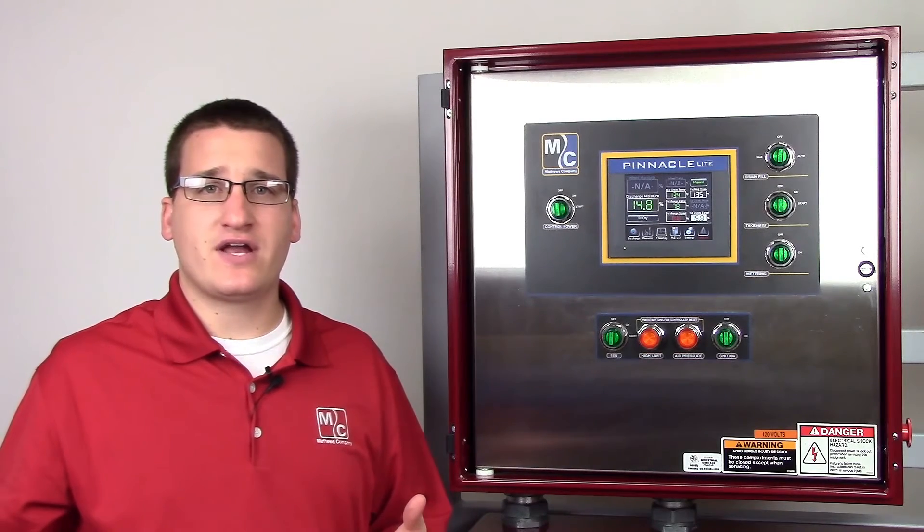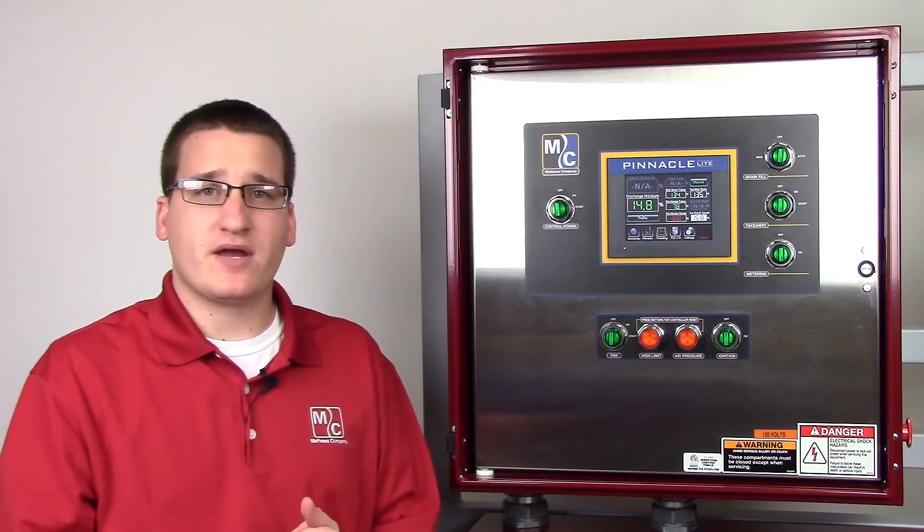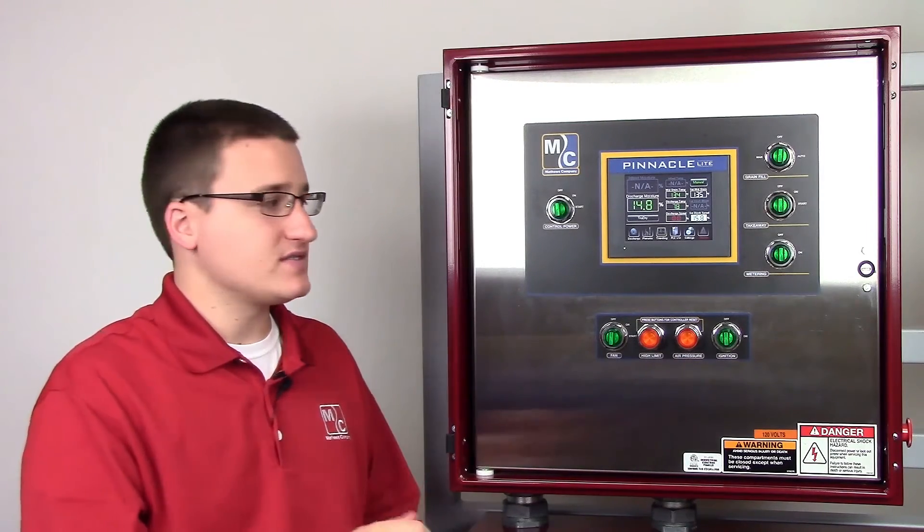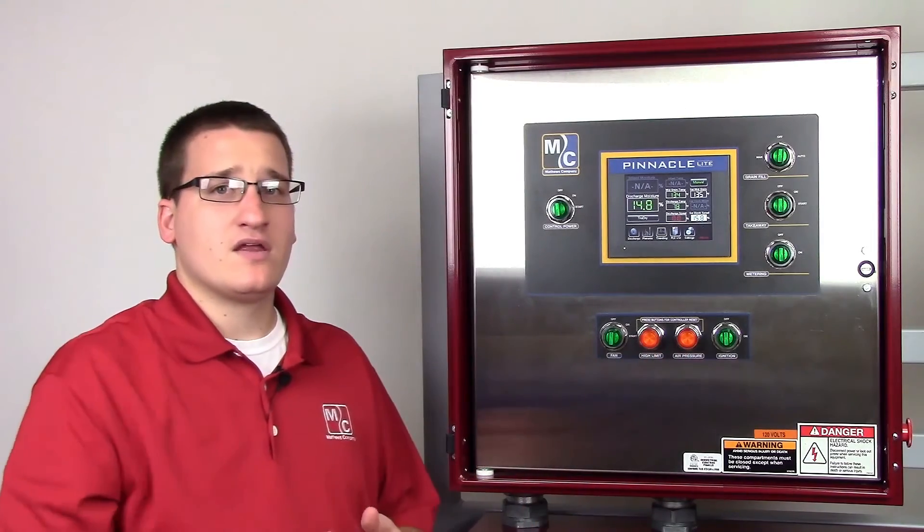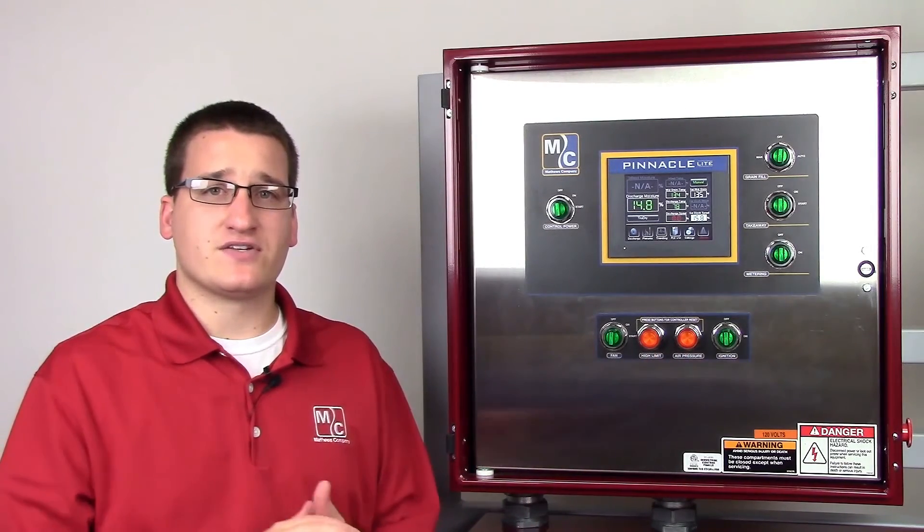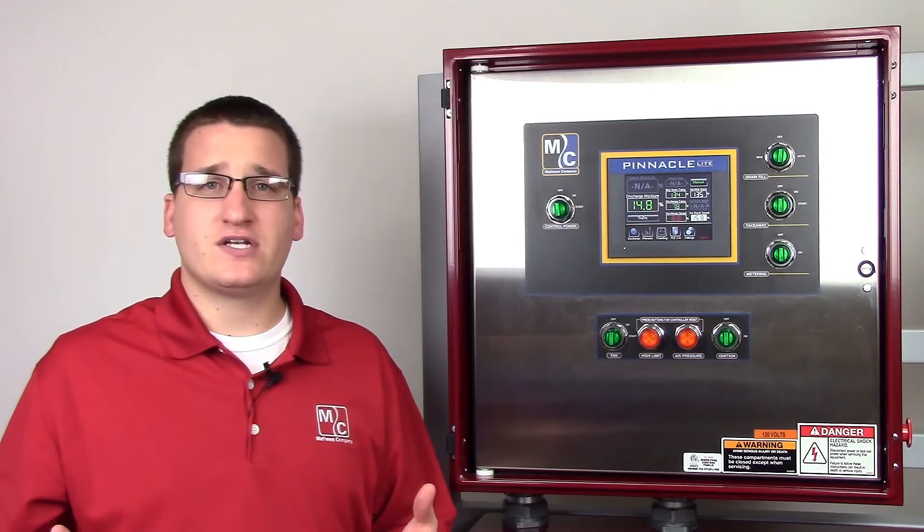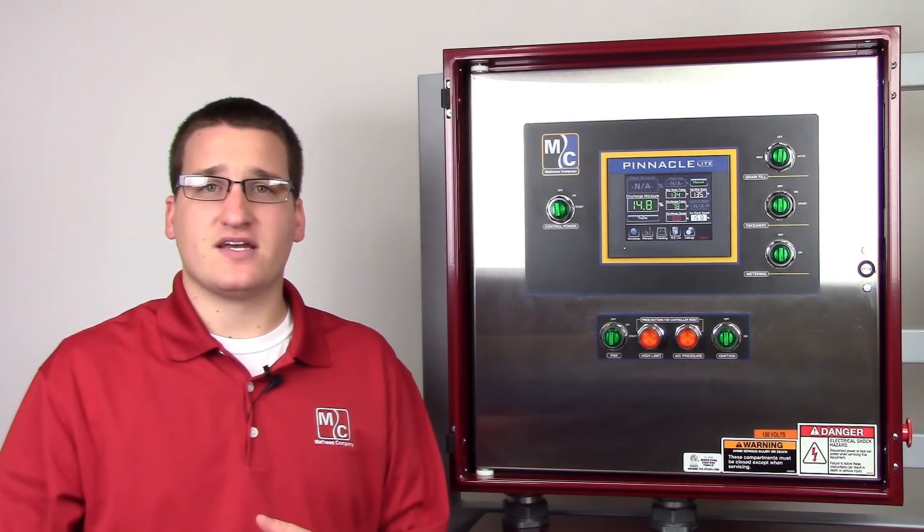You may want to reset your CAL controllers. You can do this by pushing in the high limit and air pressure buttons simultaneously. This will prevent nuisance alarms on startup. You've just shut down the dryer in a way that's easy to start up the next day.